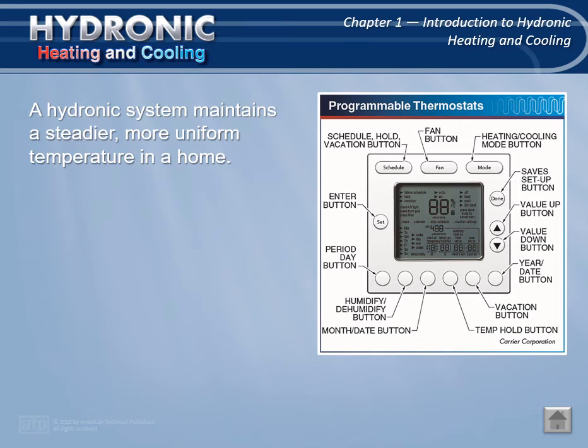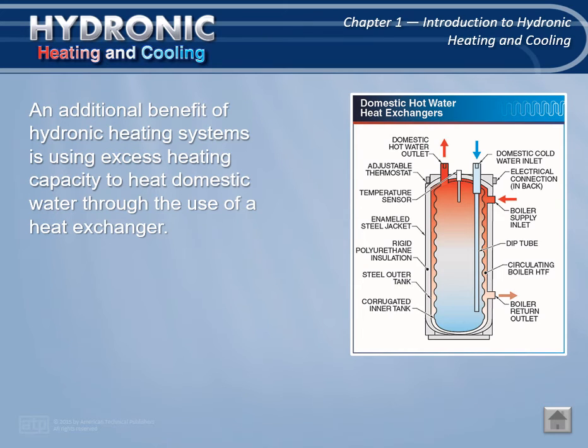Hydronic heating systems must have enough capacity to provide heat transfer fluid that is warm enough to adequately heat a conditioned space on the coldest design day. A hydronic system maintains a steadier, more uniform temperature in a home. Some other benefits of hydronic heating are that, for a given temperature rise, liquids can absorb almost 3,500 times more heat than the same volume of air. Therefore, far less water than air is needed to distribute the same amount of heat, meaning that hydronic water distribution can use piping that is much smaller than the equivalent air ductwork.